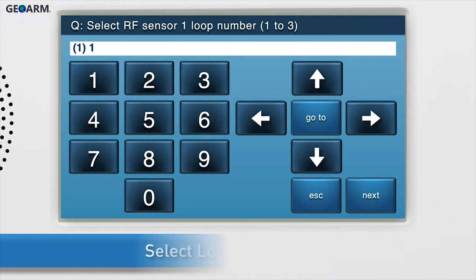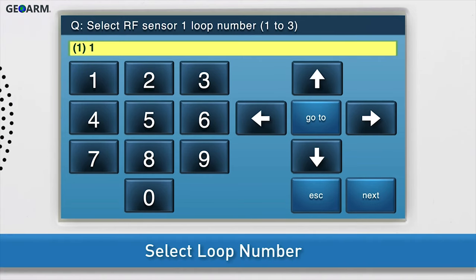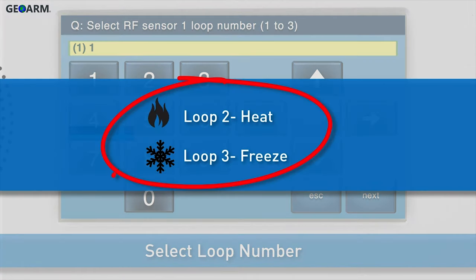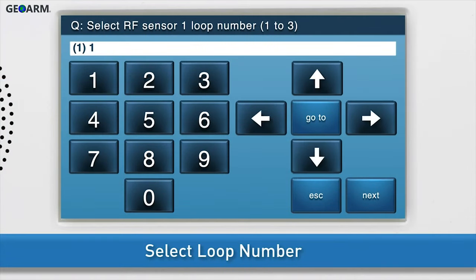Next, select the loop number. Select Loop 1 for the smoke detection feature. We will not be using loops 2 and 3, as these are reserved for the heat and freeze functions. Press the down arrow to go to the next sub-question.